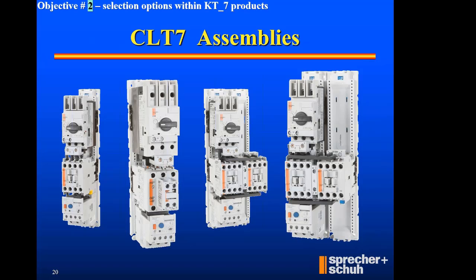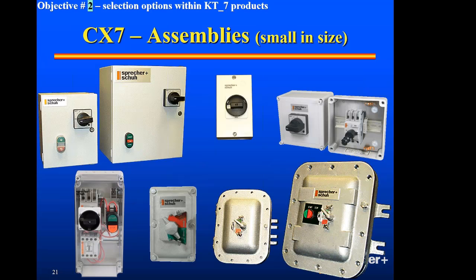And visually, I gave you the description of a 3-component starter using a KT7, and that's what I've got on the screen here in one assembly number. We call it a CLT7. T as in Tango says that we're going to add an overload relay at the bottom of that assembly. And now you can envision, if I use a full featured overload at the bottom of that assembly, it provides a port where I can plug in specialty features like ground fault and thermistor, and I can even do Ethernet IP on the side of that. So that opens up the options. That's just letting you know what a CLT7 is. And up to now, we were talking about open components.